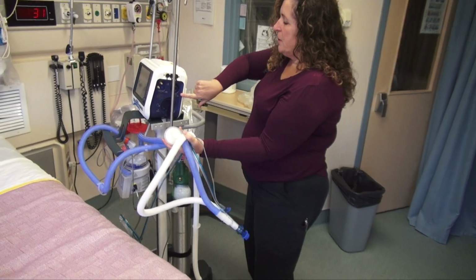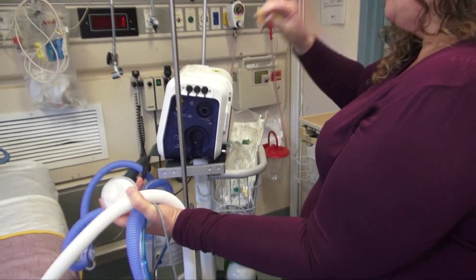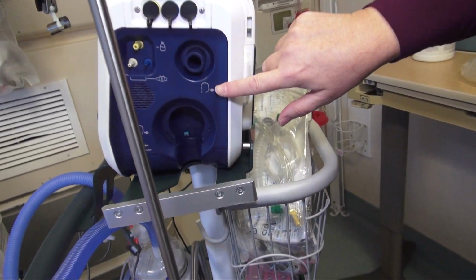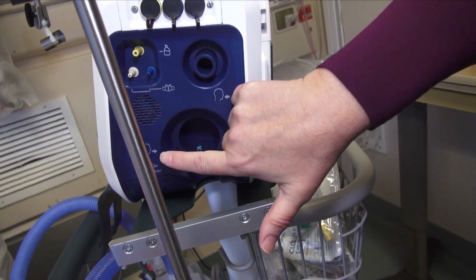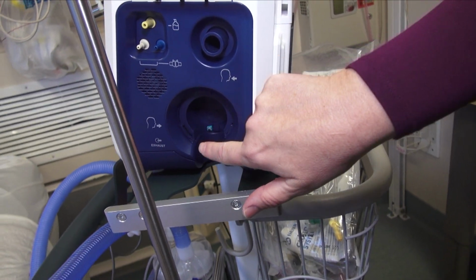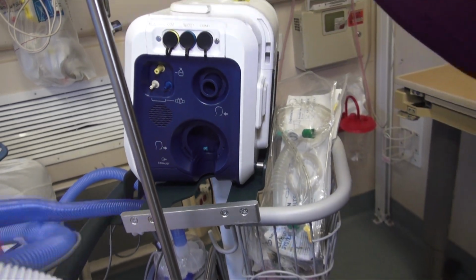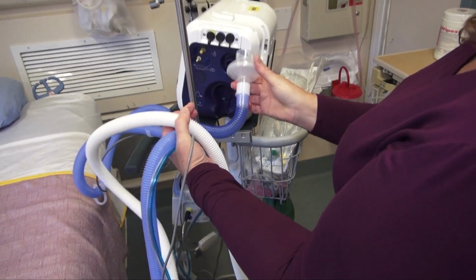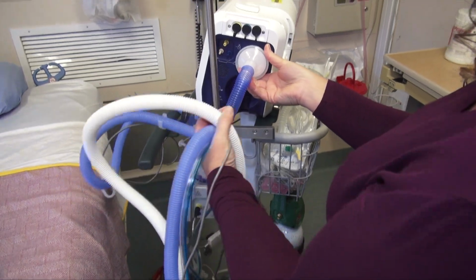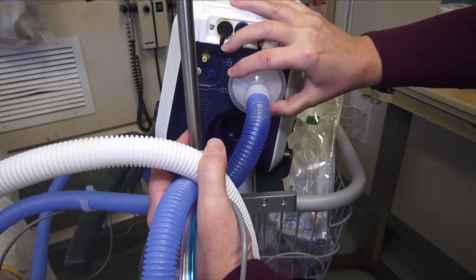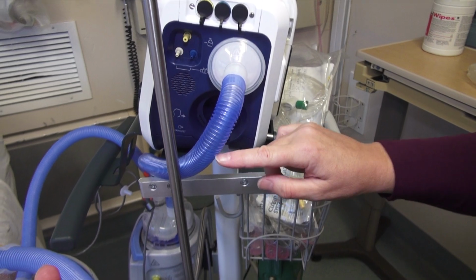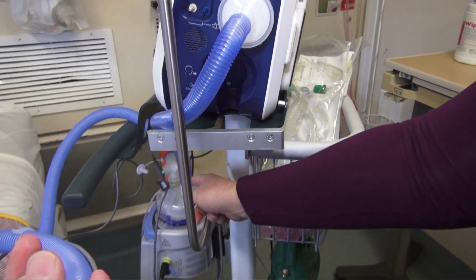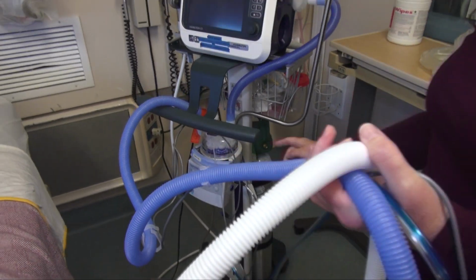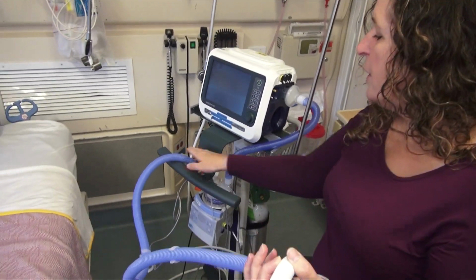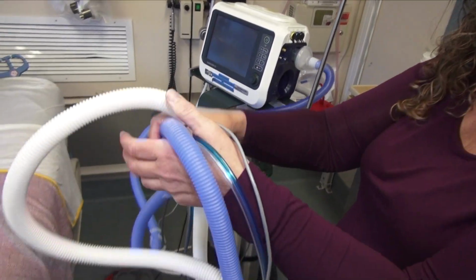On the ventilator, we have inhalation, the little man with an arrow going in, so inhalation, and a little man blowing out, exhalation. They won't be hard to distinguish, but best by just what's going on them. So you press in your first inspiratory limb, which goes into the humidifier and then comes out of the humidifier into the next blue limb and goes to your patient.